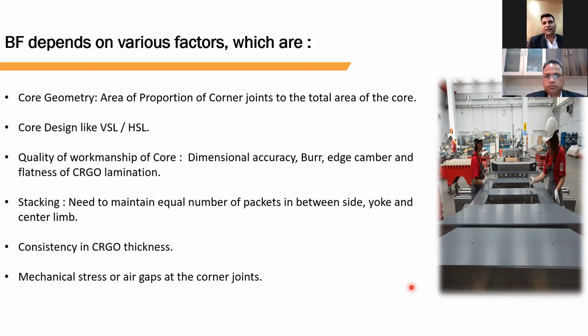We need to understand that maximum concentration of flux happens on the limb, because our windings come on the limb only, not on the yoke. So if a designer increases CRGO weight in the yoke portion rather than the limb portion, that impacts the no load loss calculation. This is an area where most people on the CRGO processing side are not checking their design properly, and they just go with simple calculation of no load losses, incurring issues after supply. So core geometry is also an important part affecting no load losses.